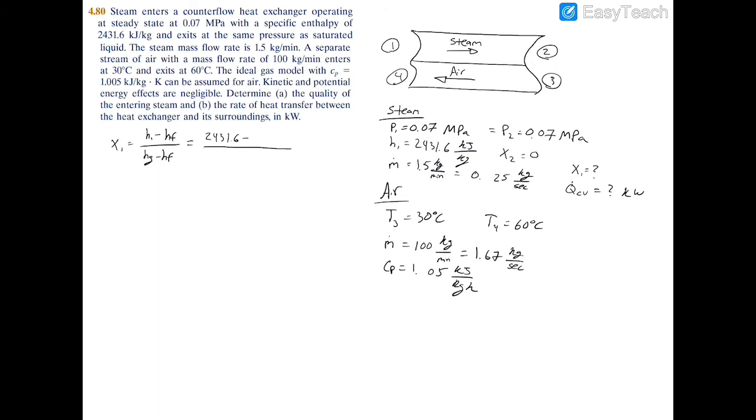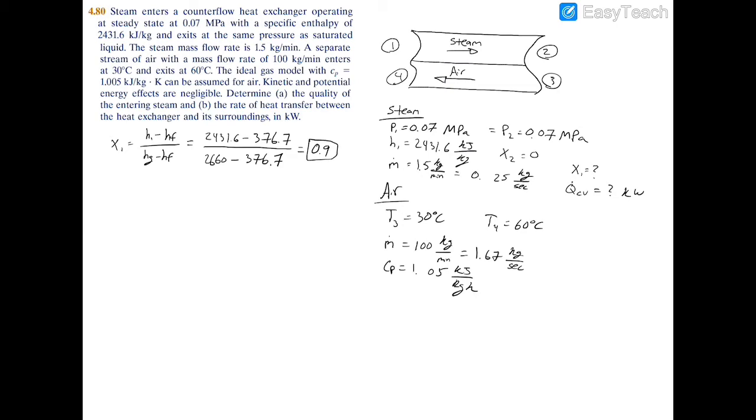So therefore we can use hf is 376.7 and hg is 2660. So we can fill out the rest of this formula as 376.7 on the top and 2660 minus 376.7 on the bottom, and this all equates to the quality being 0.9. And that actually makes sense because steam should be closer to being a saturated vapor, and also we're much closer to the saturated vapor content rather than the saturated liquid content.